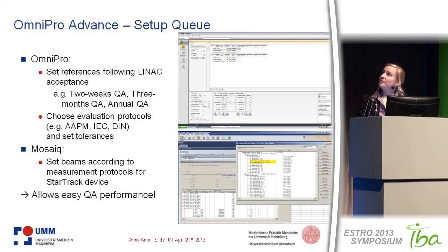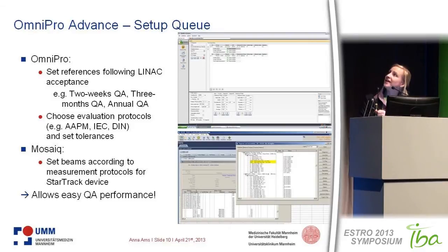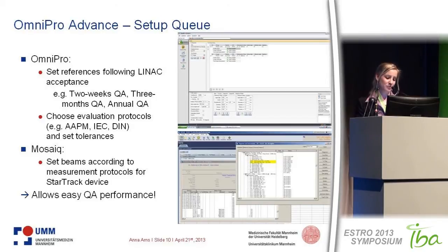Here is the setup queue in more detail. Since we have Elekta Linacs, the system controlling the Linac in clinical mode is the Mosaiq electronic recording system. To optimize QA performance, you can define your two-week QA, three-month QA, and annual QA all in the setup queue. In Mosaiq you can generate a QA patient and order the same beams you want to irradiate, making it a straightforward and easy QA workflow.